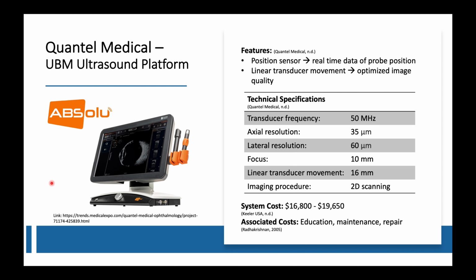The technical specifications are similar to what we have seen and discussed in the previous slides. Transducer frequency operates at 50 MHz and provides both axial and lateral spatial resolution at 35 and 60 microns. The ultrasound wave is focused 10 mm from the transducer for sharpness and image quality. The linear transducer movement is 16 mm, and the machine provides a 2D scan.